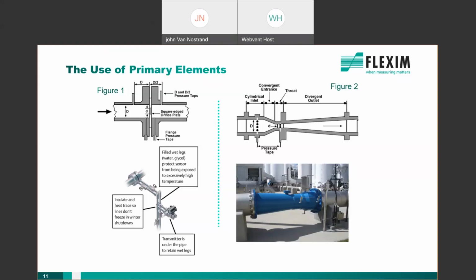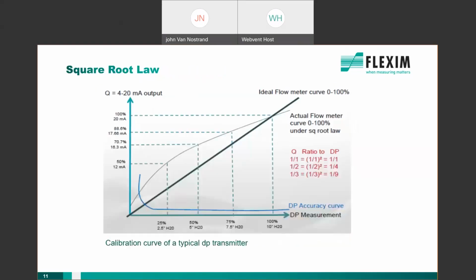So according to ASME code, there are 3 huge limitations when using these devices. A minimum velocity of about 1/3 of the flow range is required in order to measure accurately. So these meters have a turn down of about 4-to-1, and the accuracy of the primary device is plus or minus 1%, not including the transmitter and installation errors. These can be really a big deal when it comes to impulse lines and head losses from the transmitter location to where the venturi is. And then, of course, the square root law has to also be considered, which we'll touch on a little bit more here.